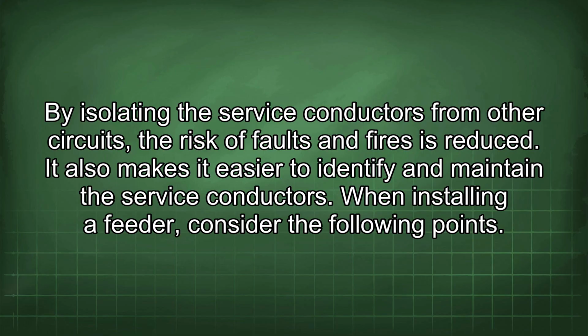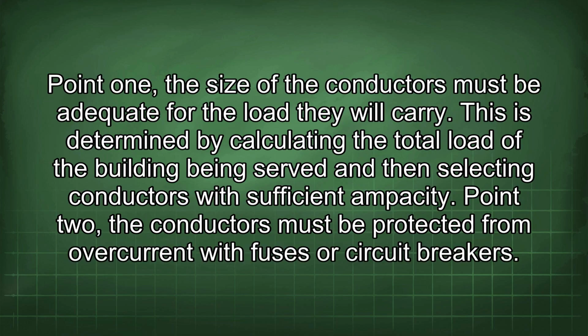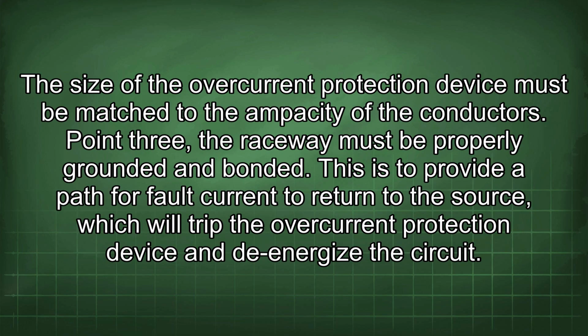When installing a feeder, consider the following points. Point 1. The size of the conductors must be adequate for the load they will carry. This is determined by calculating the total load of the building being served and then selecting conductors with sufficient ampacity. Point 2. The conductors must be protected from overcurrent with fuses or circuit breakers. The size of the overcurrent protection device must be matched to the ampacity of the conductors.